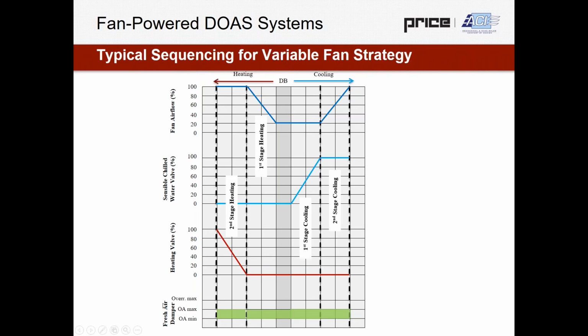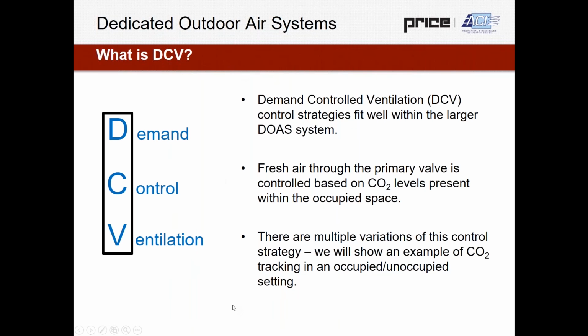One other important note here, generally on sequence diagrams, we would see some kind of primary airflow discussion. And I've left it blank here as an intentional transition point to look at demand control ventilation a little bit further and to paint the picture and communicate that this is such a perfect bread and butter, cherry on top type of solution when you look at series fan powered chilled water terminals applied within a dedicated outdoor air system.